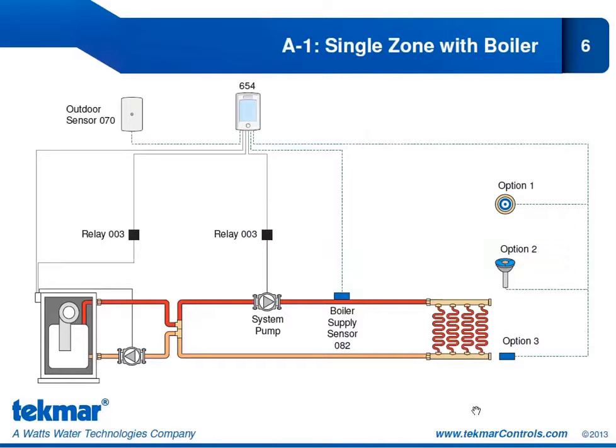Starting with application 1, where we have our single zone with boiler. Now here, the 654 is operating a hydronic snow melting system, and we're using a modulating boiler and a system pump. So you can see we have the 654 operating the system pump and giving that enable signal and the modulating signal to a modulating boiler. The boiler is piped in primary secondary to the snow melt system to allow the system pump to operate continuously during melting or idling, while allowing the boiler and the boiler pump to turn on and off as required.